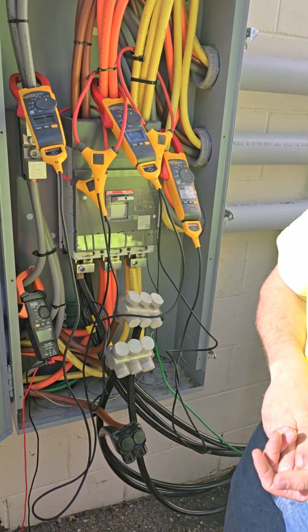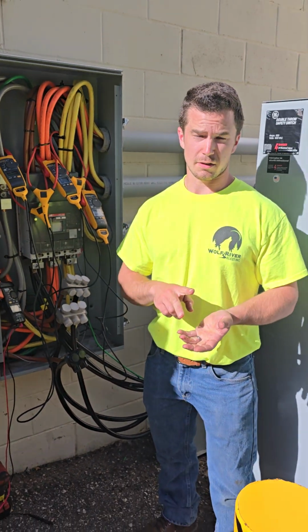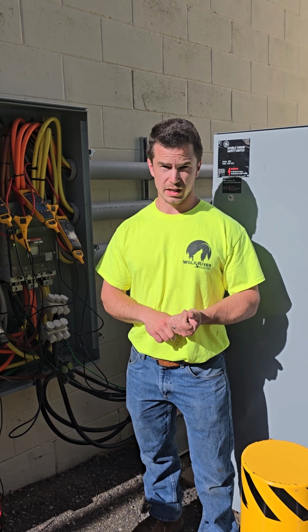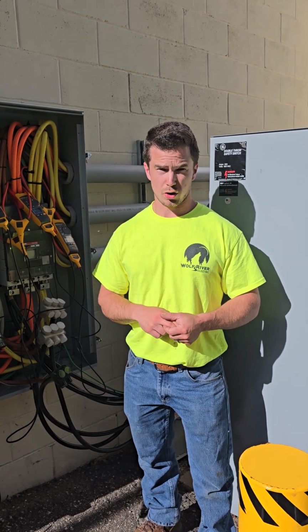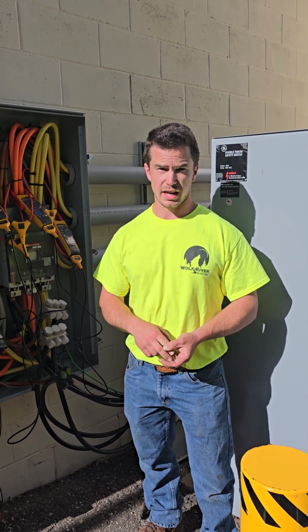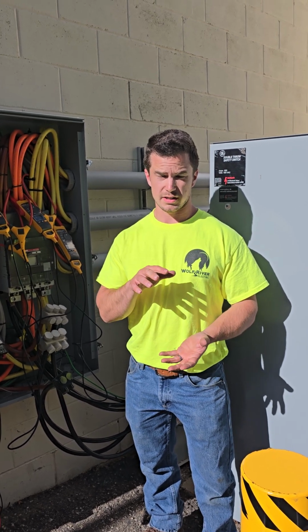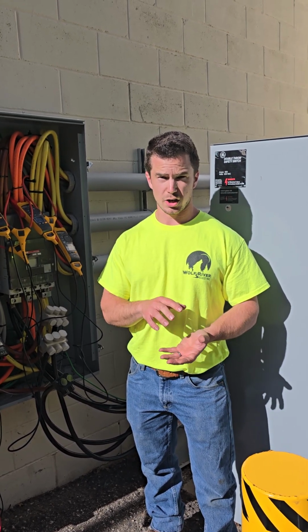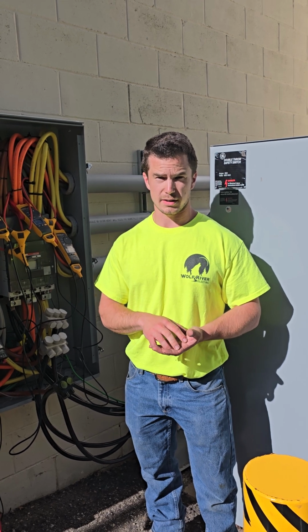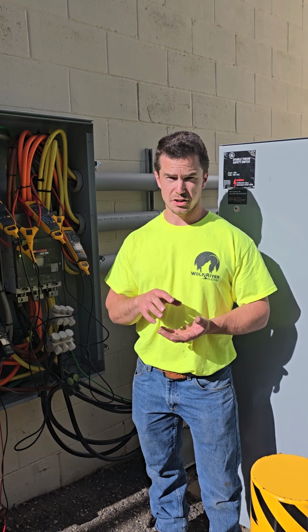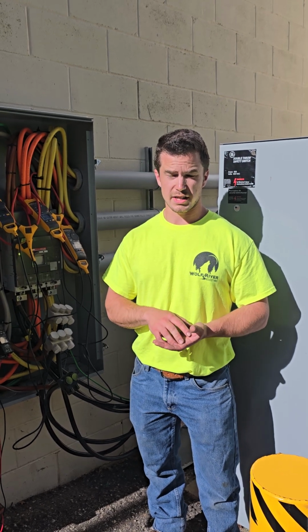I want to explain two things before I throw this phase. The first one is that when I throw a phase and the inverters stop producing, that restarts an internal clock inside of the inverters. That clock is set to 8 minutes. Protocol for Minnesota is to start after 5 minutes. Xcel's requirement is to start before 10 minutes. That's our time frame.